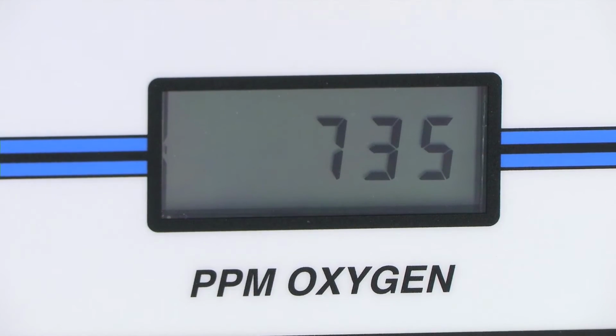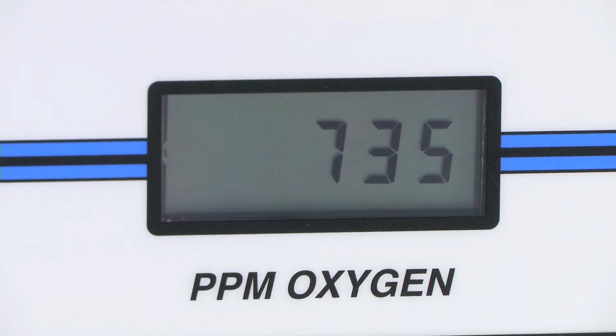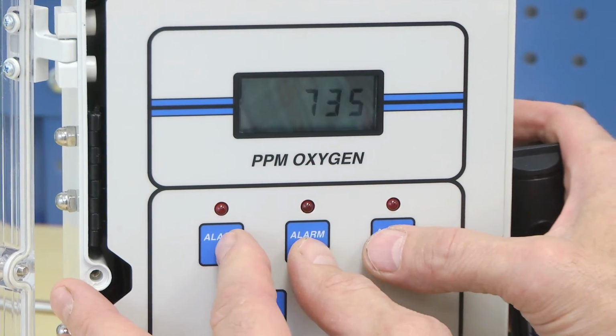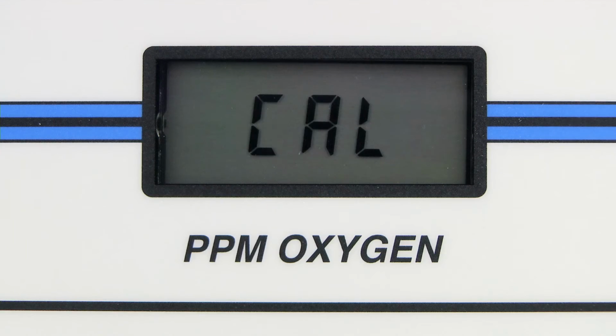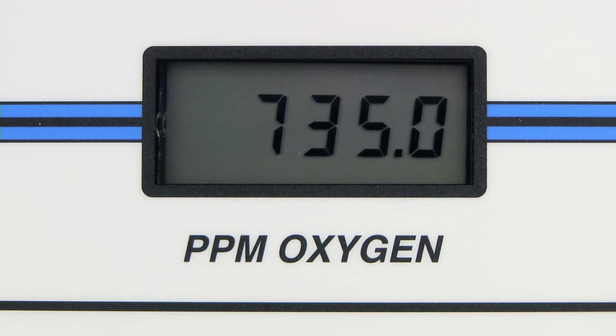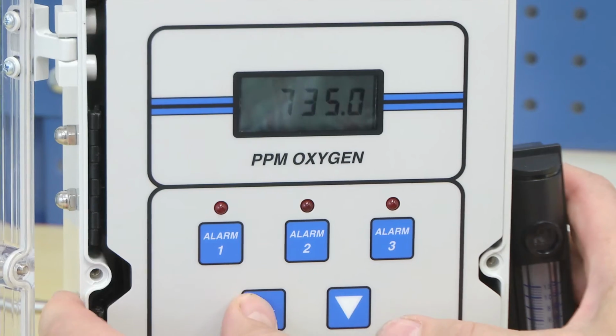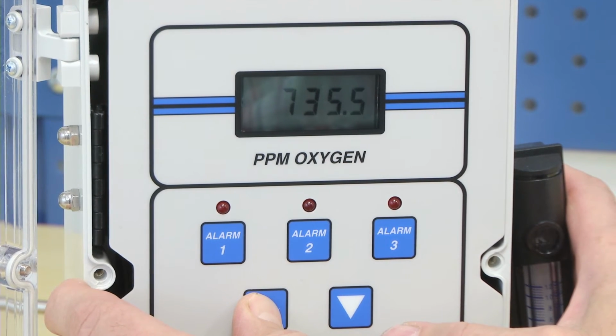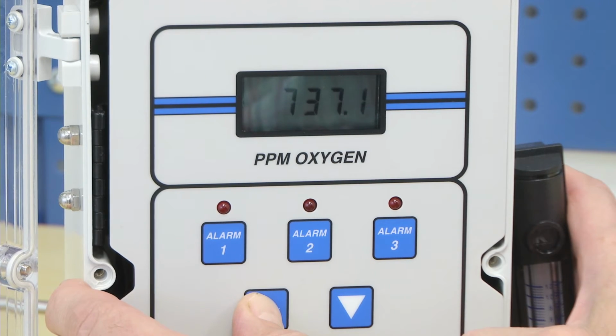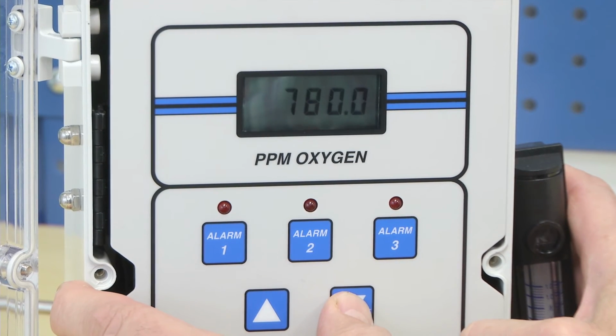To begin the adjustment process, first, simultaneously press alarm buttons 1, 2, and 3. The digital readout display will continue to show the now stable oxygen value and will also show an alternating cal message in the display. This means that the instrument is in calibration mode. Next, using the up or down arrow push buttons, press the appropriate button to adjust the display to read the 779 ppm value of the certified gas. In this case, I will use the up arrow to increase the reading.